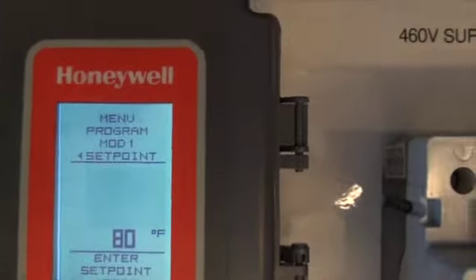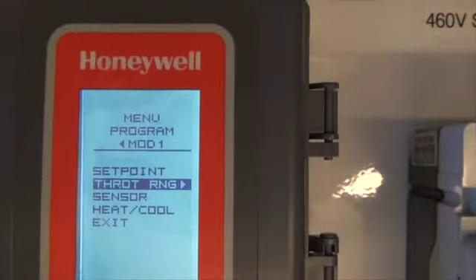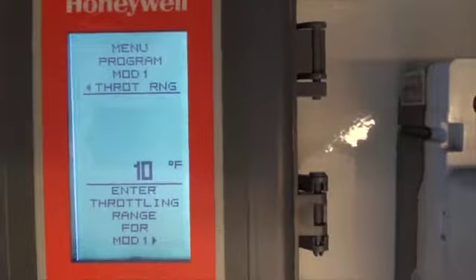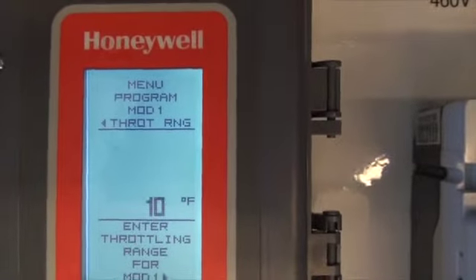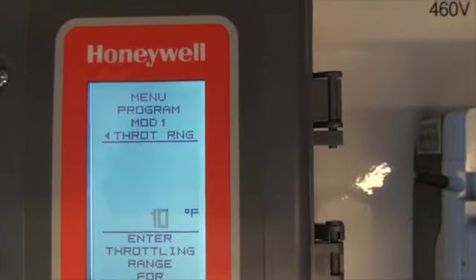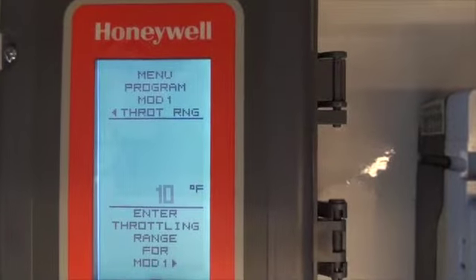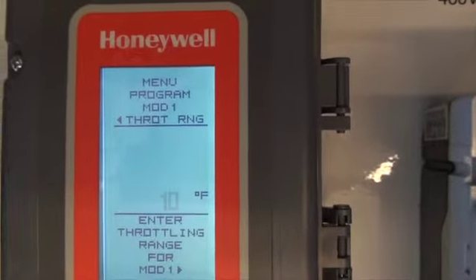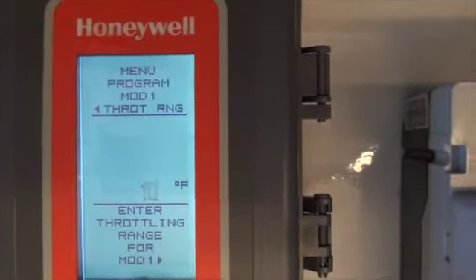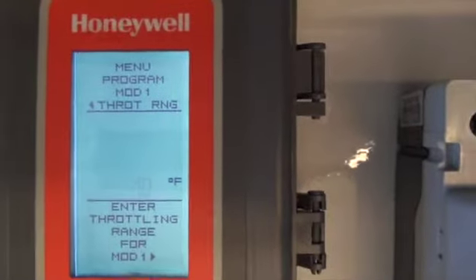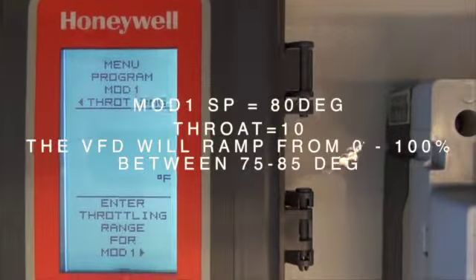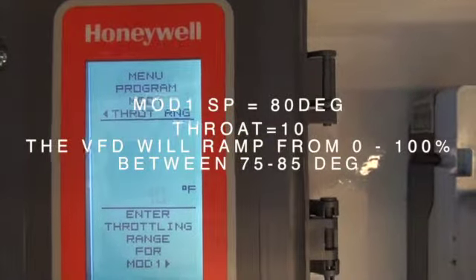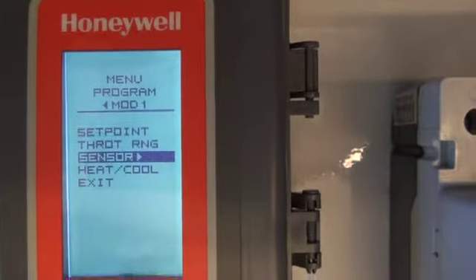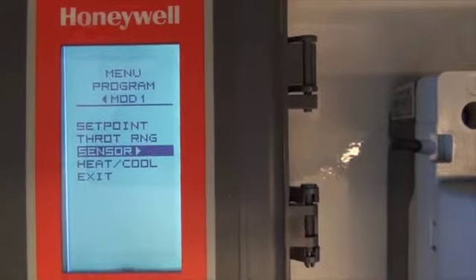Again, the next parameter is locked in at 80. It goes to throttling range. This is key because throttling range, which I like to set at 10 degrees, means that if your set point is at 80 and your throttling range is at 10, at 75 degrees it will begin ramping the drive up, and at 85 it will be at 100%. That's key. I like to keep it there because it provides a nice smooth control when you've got a 10-degree throttling range.